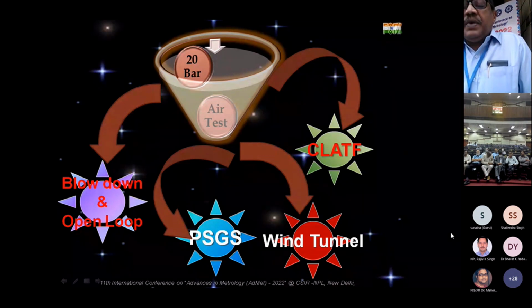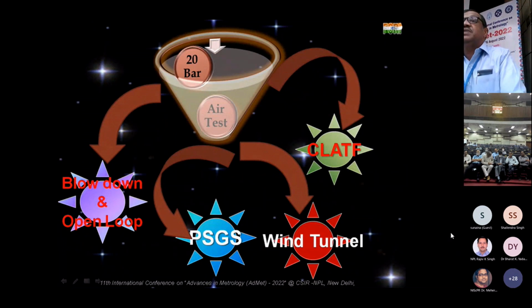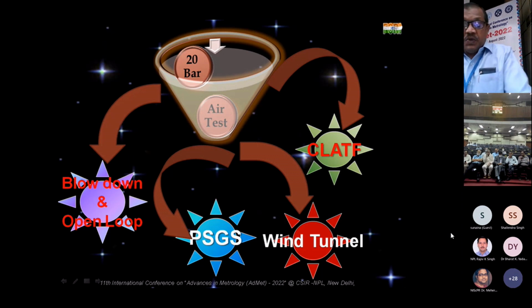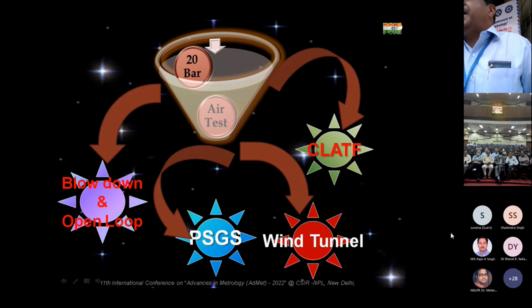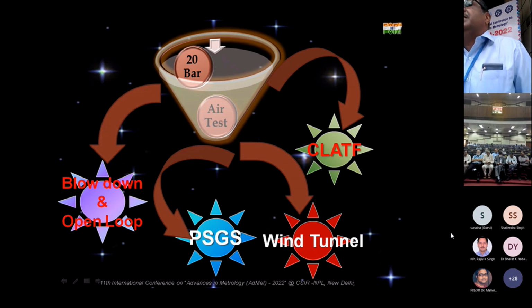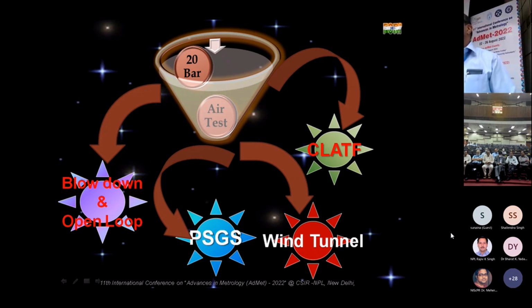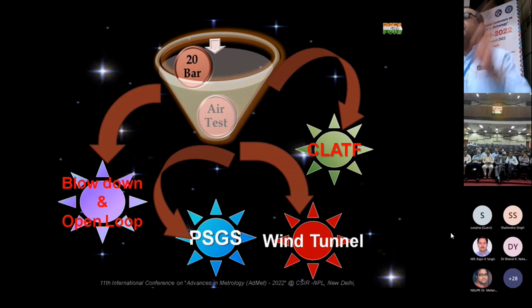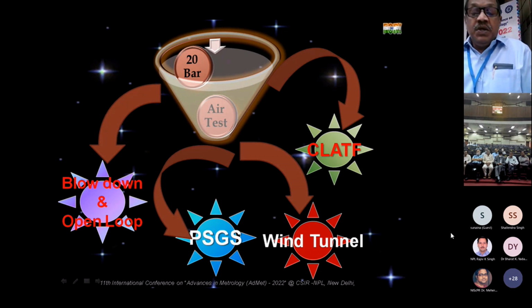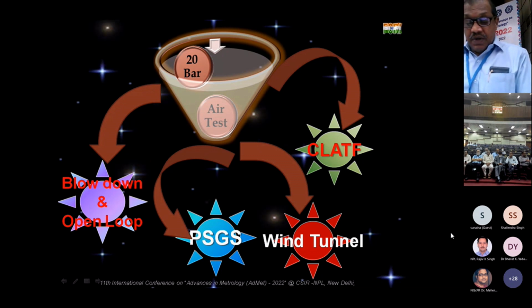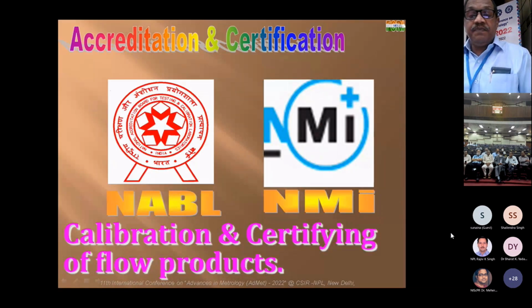In the CLATF, closed loop air test facility, we use turbine meters as reference meters, which were initially calibrated at PTB facilities in Germany and NMI facilities in the Netherlands. After establishing this facility, it is very difficult to send those meters back to those calibration facilities, because either we have no reference standard for half a year, or we should have a parallel set of meters. If one set has gone for calibration, we use the other set, and routinely we have to send it. It is very costly and time consuming. So we thought of making a primary gravimetric system for air, and I will detail that particular facility.